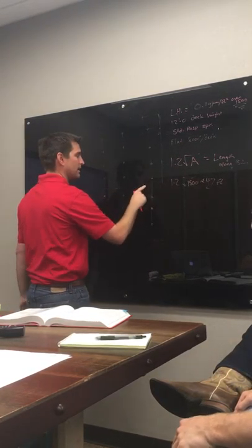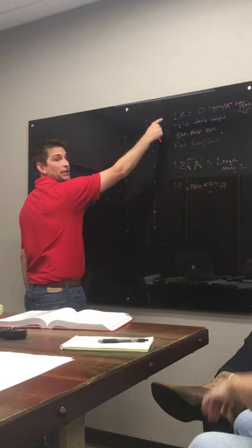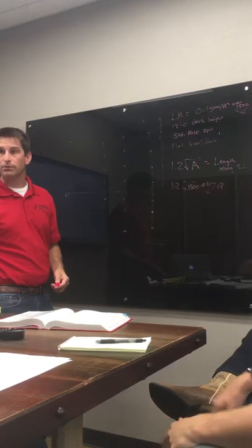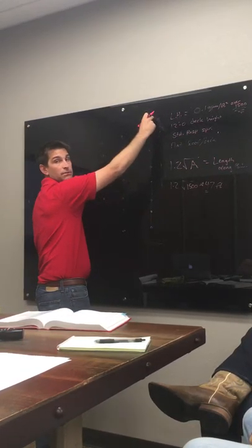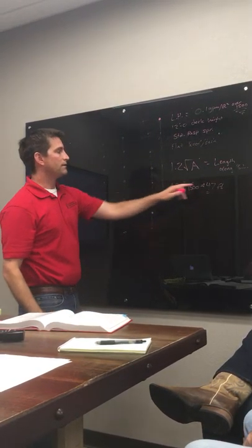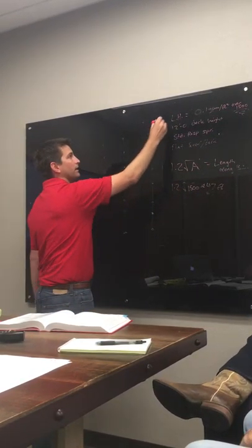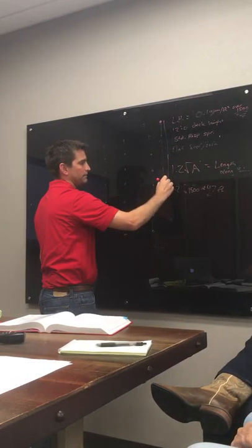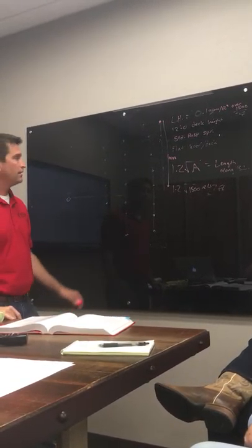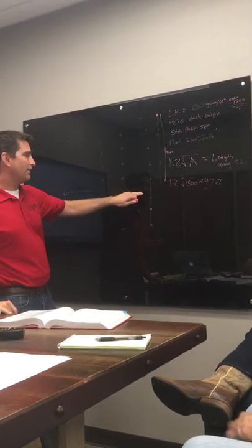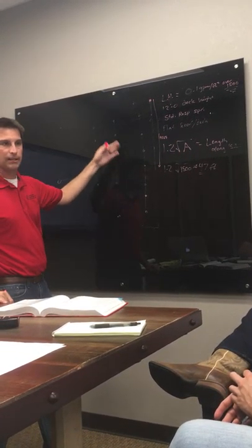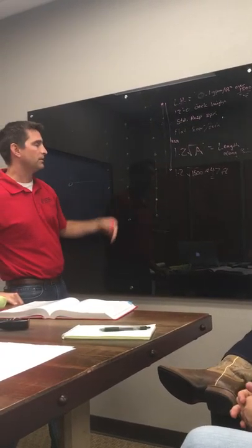So when I come here, I'm gonna say, all right, my farthest point is this corner of the building, and my design area covers what my sprinklers protect to. So this sprinkler's protecting all the way to this wall and this wall. I spaced it, right? So my remote area starts here, and I've gotta go at least 47 feet along the branch line. I find out where that falls. And it doesn't matter. I don't care where the main's at. I don't care if the main's down here or if the main was here. You cross the main as if it wasn't there. If you're not to it, then you do your 47 feet.